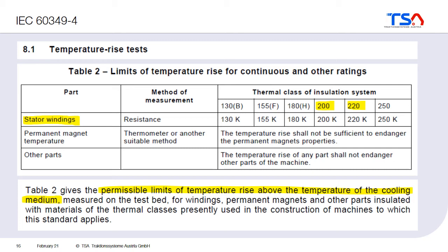The temperature rise test is one of the most important tests when you have finished a new type of machine. With this test you run the machine for a certain time — it can be a specified time like one hour, but most of the time it is a continuous heat run, meaning the machine is run until thermal steady-state operation is reached. At the end of the test you check the different temperatures within the machine, and one of the most important parts is the stator windings with their insulation.